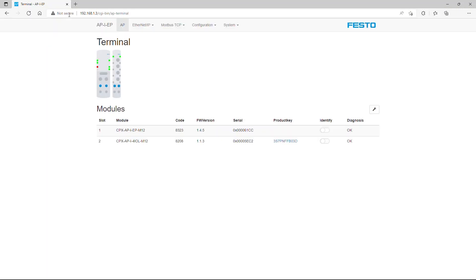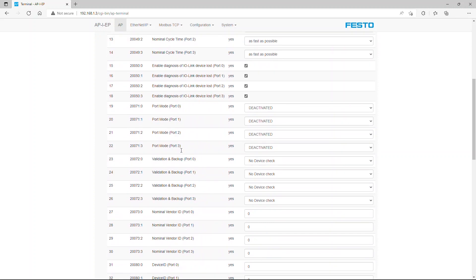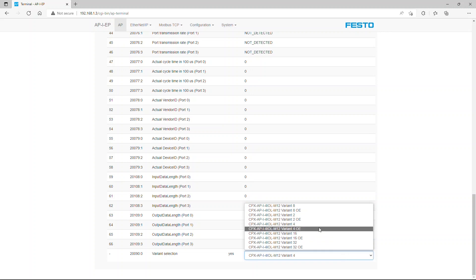IO Link Master Port Configuration. Make sure the PLC is disconnected from the CPX API EP head module during variant parameter selection. Power restart the CPX API EP module to activate the new configuration, then reconnect the CPX API EP module with the PLC. Select the IO Link variant based on your target device process data size.